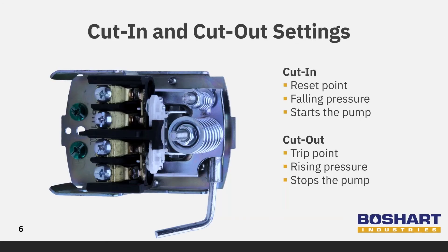All pressure switches have two operating points known as the cut-in and cut-out. The cut-in point, also known as the reset point, is a result of falling pressure and starts the pump. The cut-out point, also known as the trip point, is a result of rising pressure and stops the pump.